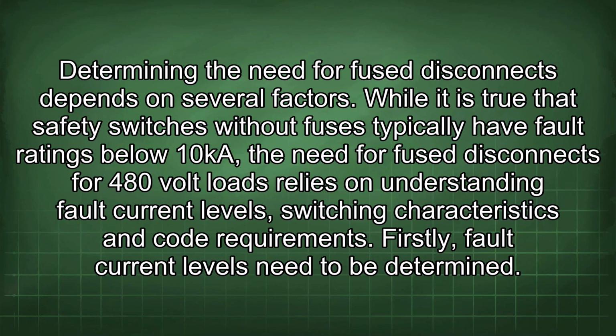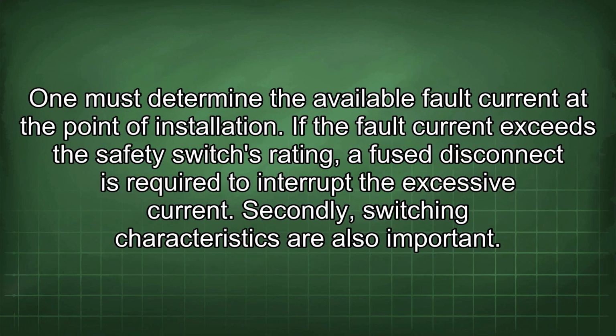Determining the need for fuse disconnects depends on several factors. While it is true that safety switches without fuses typically have fault ratings below 10 kA, the need for fuse disconnects for 480-volt loads relies on understanding fault current levels, switching characteristics, and code requirements. Firstly, fault current levels need to be determined. One must determine the available fault current at the point of installation.